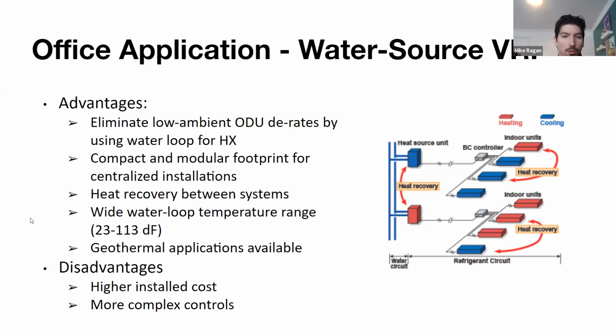Now this next bullet point is an interesting one. With heat recovery systems, the advantage that you get is that for zones that are in cooling mode, you can utilize that heat and send it elsewhere in that refrigerant network to a zone that is in heating mode. So we're taking all that heat from that server room that's just heating up and it needs cooling, and we're delivering that to the conference room where everyone is waiting for everything to start heating up in there.